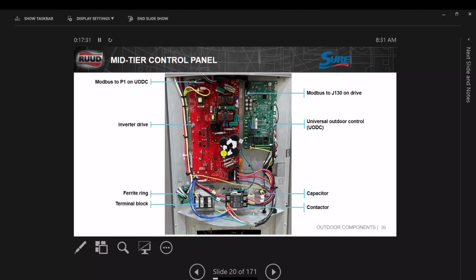So we have our inverter board there, that big red board. Over here on the right, you see a capacitor and a contactor, right? Does that raise a question? Wait a minute, that's an inverter. Why does it have a contactor and a capacitor in it? Both of these are supposed to be variable speed. That's part of the 3-stage operation.